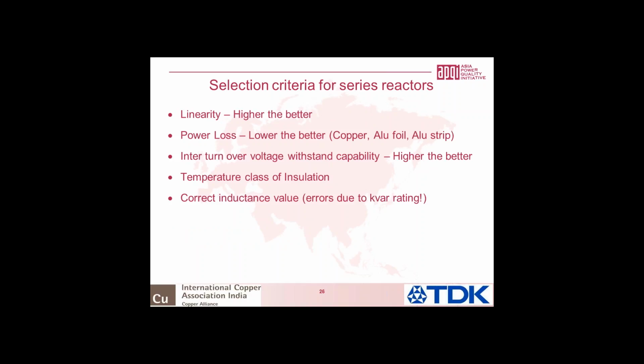Another key parameter is the inter-turn voltage capacity, and the temperature class of the insulation, higher the better, and the correct inductance value. This is the key because most of us oversimplify life by looking at everything as per kVAR. kVAR is a derived parameter. kVAR is a product of voltage and current, right? So unless you specify kVAR at what voltage or what current, it's a derived parameter. Whereas when I buy an inductance, I buy a certain millihenry. I don't buy kVAR. kVAR is incidental. So my request is, whenever you choose inductance for tuning or detuning, be particular about the millihenry and the current capacity rather than the kVAR.